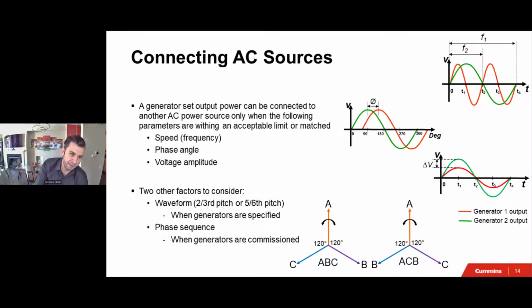Handling those speed, phase, and voltage amplitude is called synchronization. We'll talk about that next. But there are two other factors we need to consider. There is the waveform: when you're specifying alternators or generators, you've probably heard the terms 2/3 and 5/6, and this has to do with how the generator is constructed. That only comes into play if you're specifying a new system.